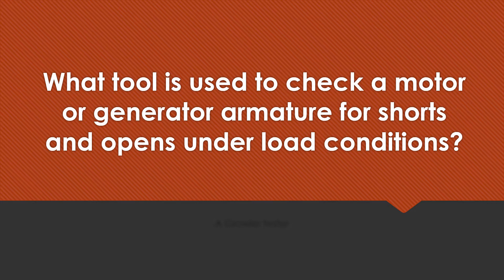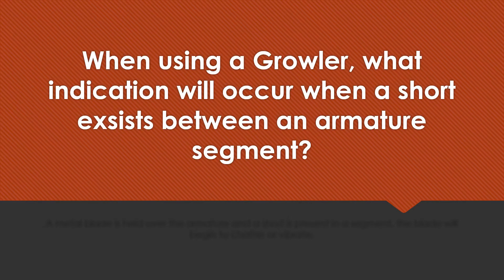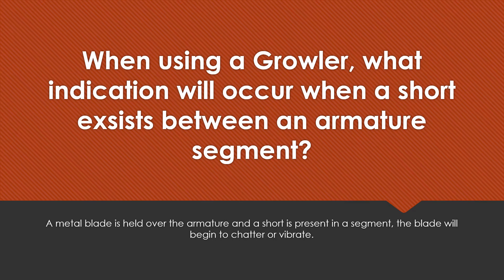What tool is used to check a motor or generator armature for shorts and opens under load conditions? A Growler Tester. When using a growler, what indication will occur when a short exists between an armature segment? A metal blade is held over the armature, and if a short is present in a segment, the blade will begin to chatter or vibrate.